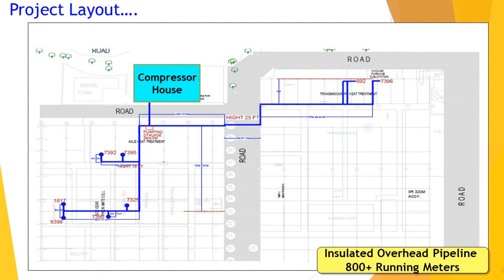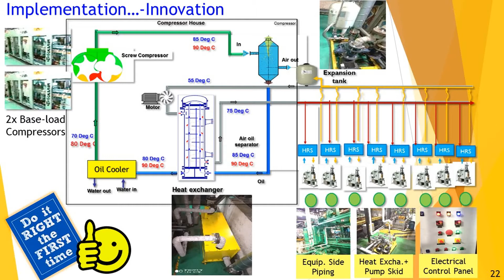From the compressor house, you can see about 800 running meters of insulated overhead lines were laid. And this is the actual implementation of the project. We have taken both the base load compressors, but at one time only one compressor is running. We can isolate one compressor. There is a heat exchanger which recovers the heat from the oil. There is an expansion tank to take care of the circulating water. And on the equipment side, you can see the piping, a small skid on which the heat exchanger and the pumps are put. There is a control panel attached to the equipment so that localized readings can be taken. It was a first time right project.